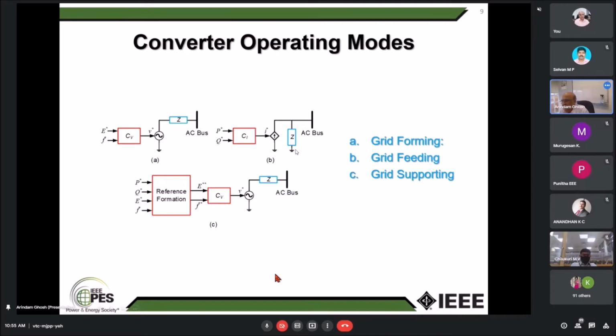So these are the two modes: grid forming and grid feeding. Grid feeding is used for things like solar PV, while grid forming is used as a UPS or islanded power supply. And there's a third mode in which all the distributed generators in a microgrid operate, using P, Q, voltage magnitude, and frequency.